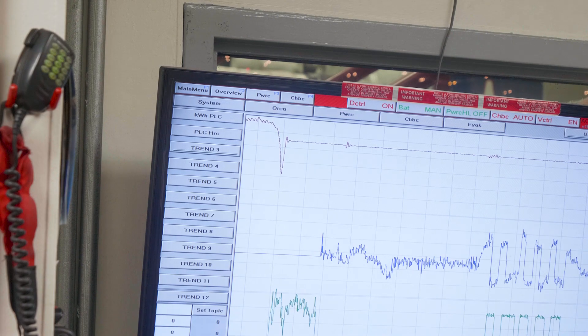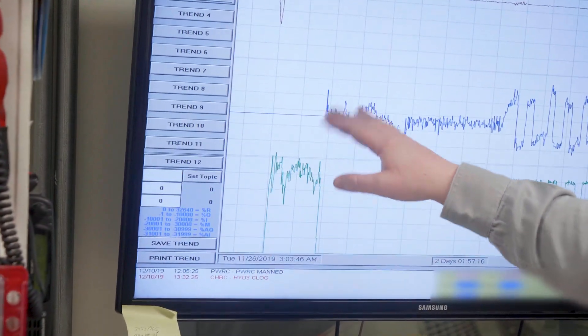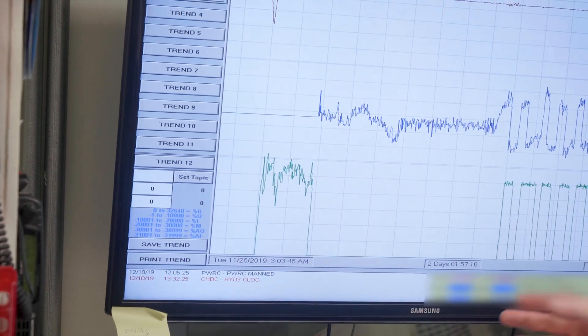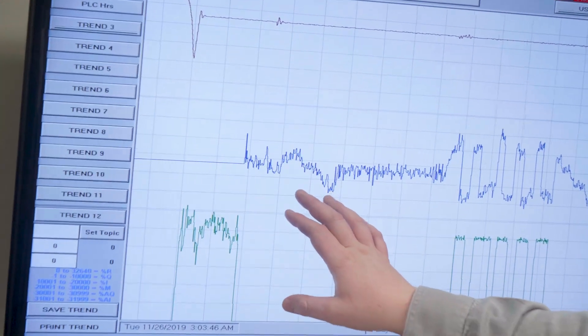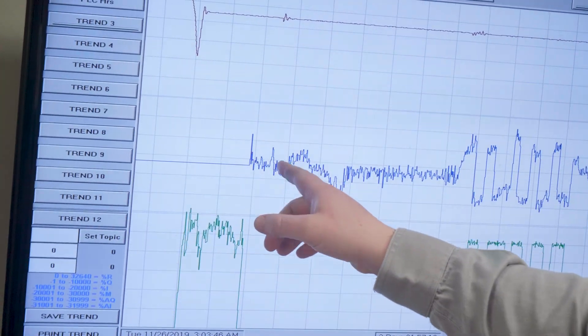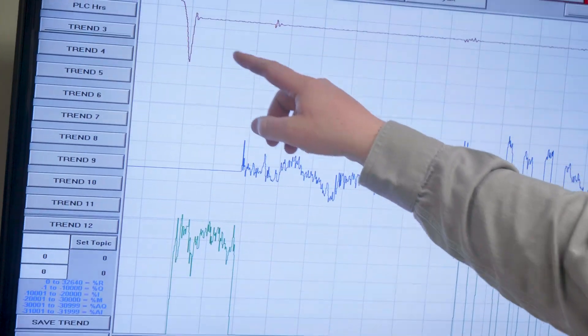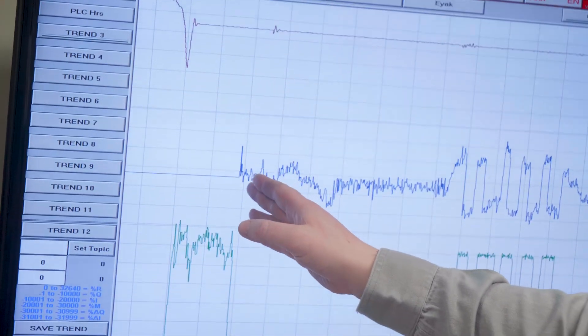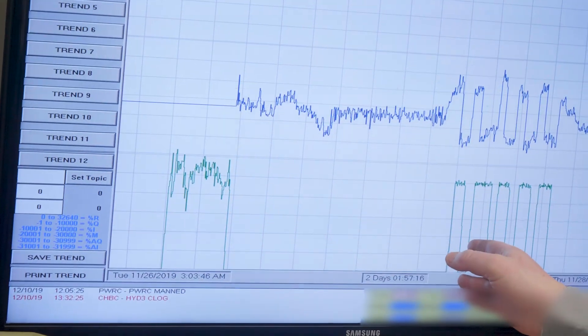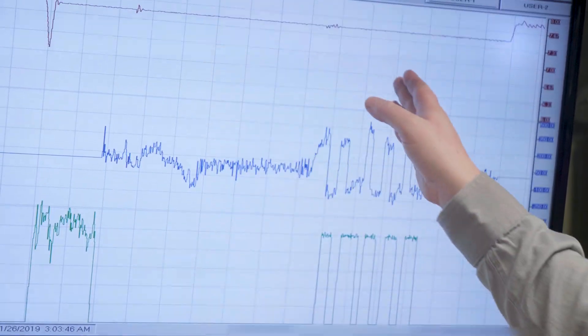The water dropped down and we started a diesel to provide spinning reserve. The operator saw that and decided we had automated the battery enough to feel comfortable with it. We put it in automatic — basically a test mode — and left it on. When we put it in auto it took over as spinning reserve, shut the diesel off, and we were back to Power Creek running with just enough water and the battery on as spinning reserve. We ran with the battery on and just hydro for about thirty hours or so.